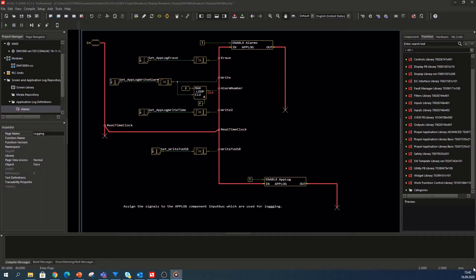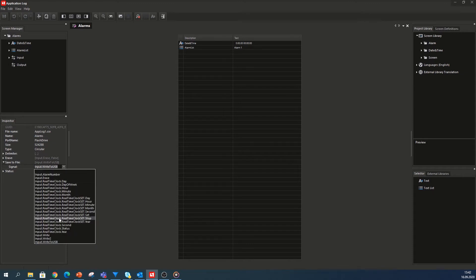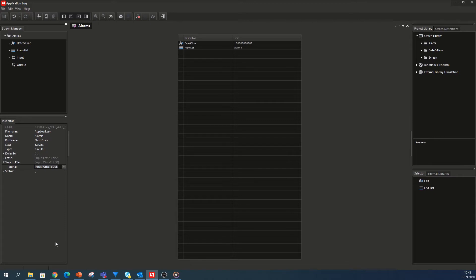I start with the save to file functionality, which is available for newer HWDs of the DP 700 and DM 10 and 1200 displays. As shown in video number 6, inside the application log editor you have the possibility to use the property 'save to file'. With this app log property you can select or assign a boolean input signal from your GUIDE application to trigger the save to file process. This process reads the application log from the flash memory on the controller and saves that file on the USB stick in CSV file format. There's no need to start and use the service tool. You can assign a display button to that signal, for example, or any other kind of command forced via your GUIDE code.